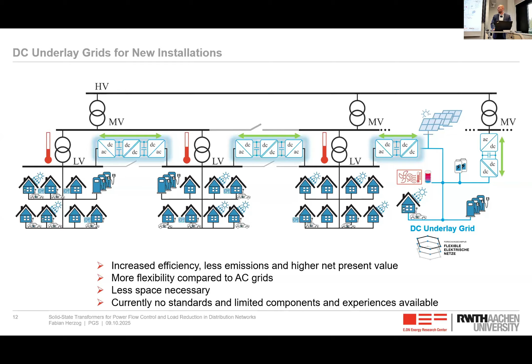Here we can also use the solid state transformer again, but we can cut some components and keep the same functionality. The advantage is increased efficiency, because components like charging infrastructure always have a rectifier, which we wouldn't need with the DC underlay grid. We shift the rectifier to a central rectifier, and we've shown in several projects that this decreases the CO2 footprint and increases the net present value of the installation.